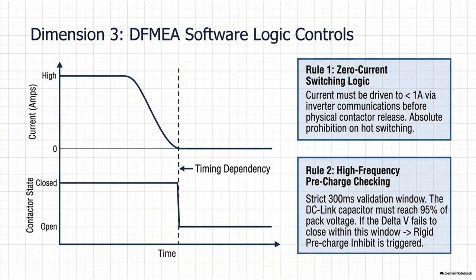Meanwhile, the BMS waits. It actively monitors the highly precise current sensor located on the main high-voltage line. It's watching the power drop. It watches the current plummet from 300 amps down to 100, down to 10. It waits and verifies until the active power draw is completely zero, or realistically, validated to be safely under 1 single amp. It waits until the high voltage line is completely quiet and devoid of energy momentum. Only when the processors verify that quiet state will the BMS de-energize the coil and allow the mechanical springs to push the massive relay contacts open. And because it's quiet, no arc forms. Because there is virtually zero current flowing at that exact moment, there is no electrical momentum, there is no plasma arc. It is a completely peaceful, harmless, cold mechanical separation.